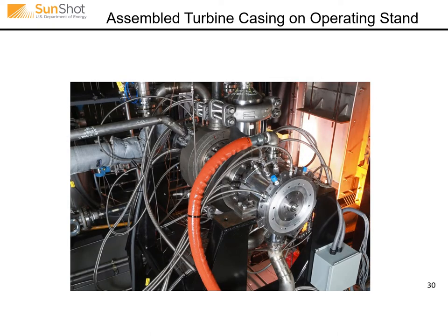This is the final installation of the turbine before insulation, showing all associated lines. The oil supply at these speeds requires around 32 gallons per minute, requiring a fairly large drain. The remaining lines are dry gas seal supply, dry gas seal vents, buffer seal supply, and a buffer seal on the end, where the air dynamometer would connect.